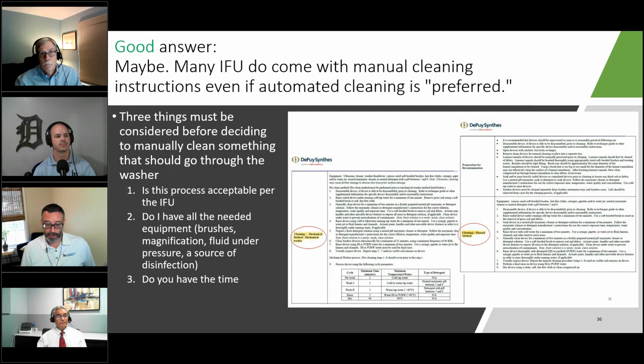Now, why do I say do you have the time? Well, because I want you to take a look here. While manual cleaning may be suggested to save time, properly following all the steps outlined in the IFU can take significantly longer than a washer would. So I just want you to know this comes from an IFU, and I just highlighted the things, and they got specific, by the way: equipment, various size soft bristle brushes. I'd like a little more than that. Various size is kind of tough for you. I guess you get a menagerie, lint-free cloth, syringes, pipette, or water jet, and then a neutral enzyme to work between 7 and 9. There are some specific items there.